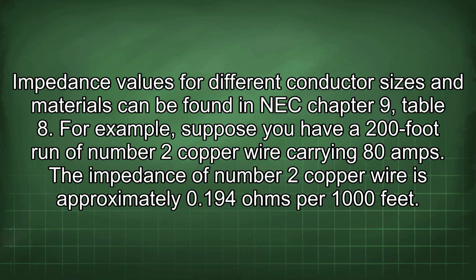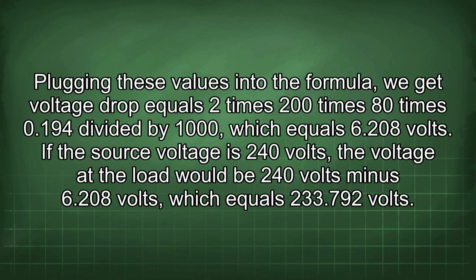For example, suppose you have a 200-foot run of number 2 copper wire carrying 80 amps. The impedance of number 2 copper wire is approximately 0.194 ohms per 1000 feet. Plugging these values into the formula, we get voltage drop equals 2 times 200 times 80 times 0.194 divided by 1000, which equals 6.208 volts.